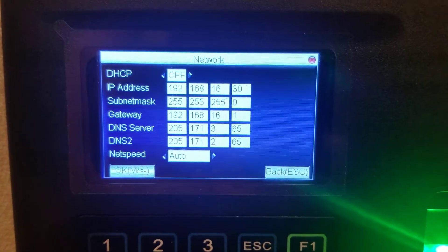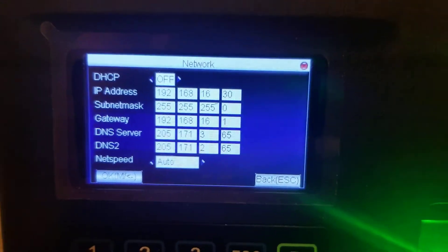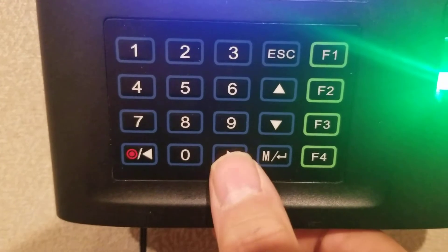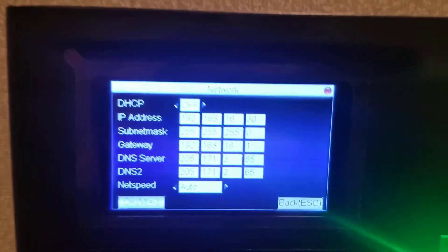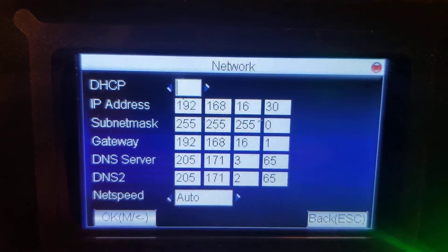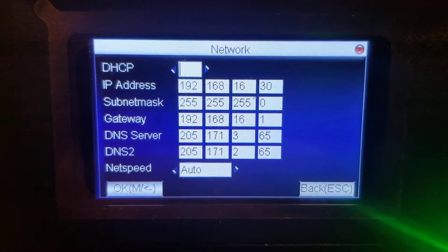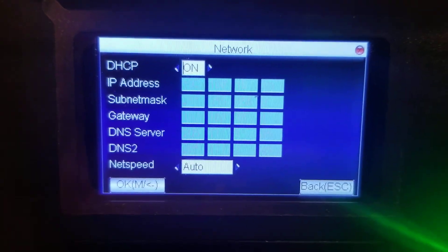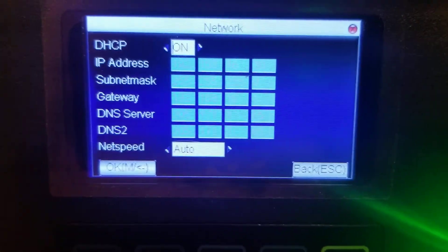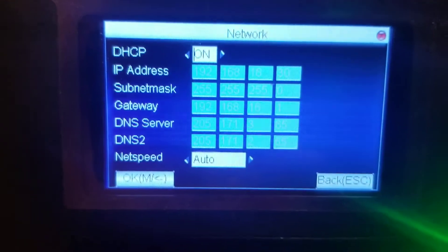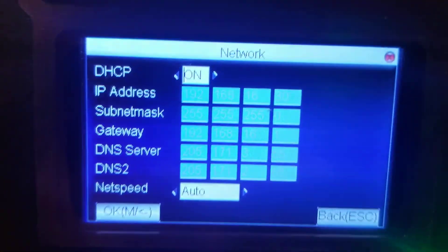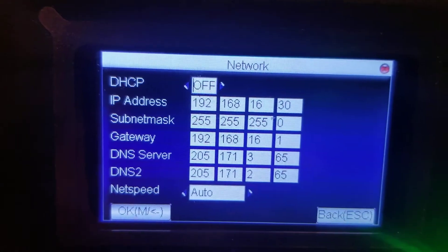We can see the DHCP is set to off, and that's exactly what we need. If you are not going to use the Wi-Fi, then you would set DHCP to on if that's what your environment needed — just click the arrow button since the cursor is already in that box, and this turns the DHCP on. If we're going to use the Wi-Fi connection, this needs to be off. Again, the arrow button while the cursor is inside the box switches this to off.